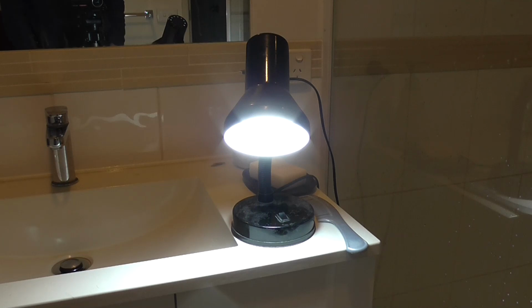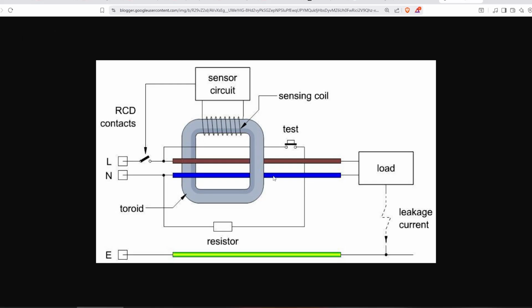Now, let's have a look at how the RCD actually works. So here's a look at a simplified circuit diagram of what's inside a physical RCD. Over here we have the live and neutral connections coming in from the distribution box, as well as our earth connections shown. Now, the neutral and the earth connections are physically joined together at the power distribution box via a large cable and a ground stake which is driven into the ground. So these 2 points are physically connected. Now, the principal working of this circuit is the current going out to the load must equal the current returning from the load. So the current going out on the live must equal the same amount of current that's being returned on the neutral.